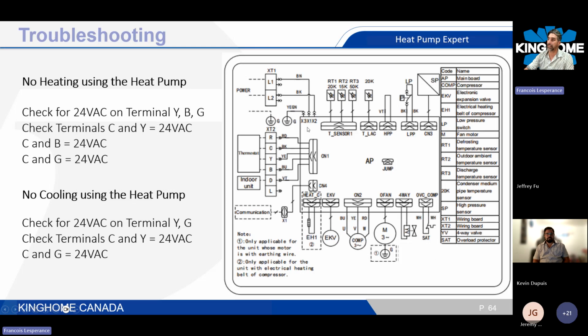So basically, when you look at that board right here, the 24 volts just stop there. So we don't use 24 volts in any protective source inside the KD unit or the KU unit. So we will use DC voltage from our low pressure switch, for example, or stuff like that. So the 24 volts will just stop at the connections right there. So if you do have power over here, it's not a thermostat issue. It means you need to look for something else.